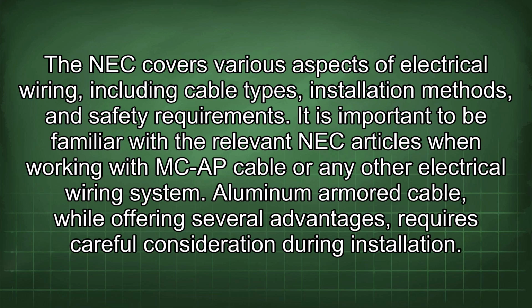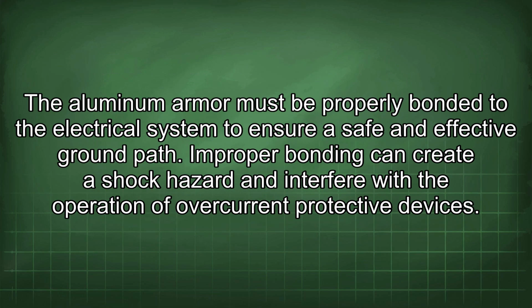It is important to be familiar with the relevant NEC articles when working with MCAP cable or any other electrical wiring system. Aluminum armored cable, while offering several advantages, requires careful consideration during installation. The aluminum armor must be properly bonded to the electrical system to ensure a safe and effective ground path. Improper bonding can create a shock hazard and interfere with the operation of overcurrent protective devices.